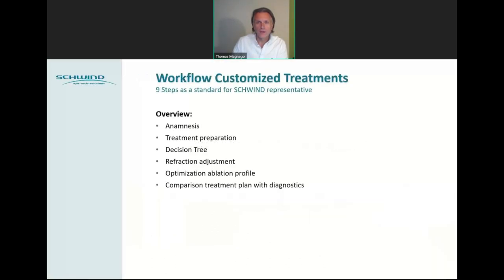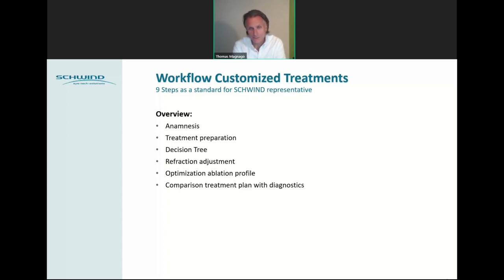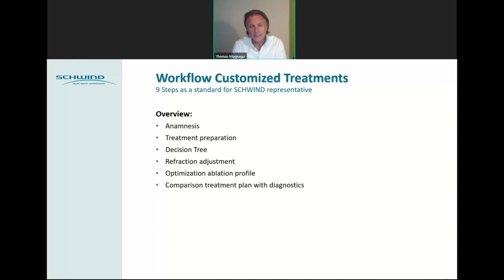It contains nine steps which we use for the analysis. It starts with anamnesis and continues with treatment preparation, decision tree, and refractive adjustment. There are multiple check steps, and the optimization of the ablation profile also involves multiple steps. We will go through this till the end, where the comparison of the treatment plan with the diagnostics gives an OK or not OK on how to continue.